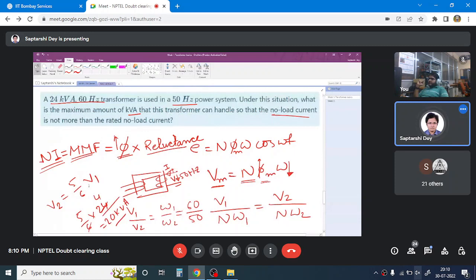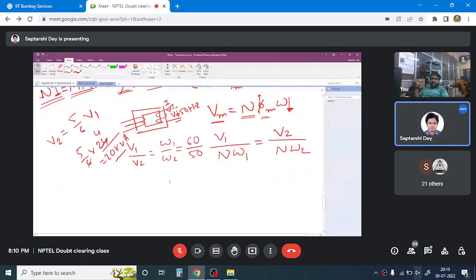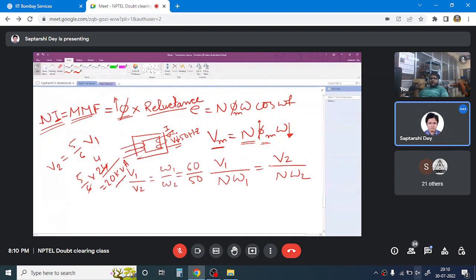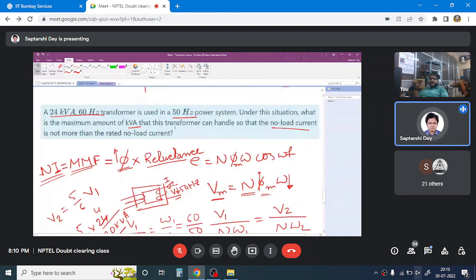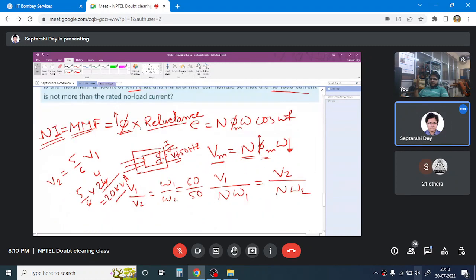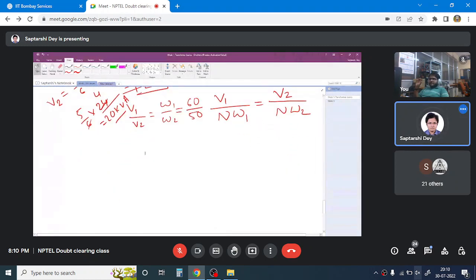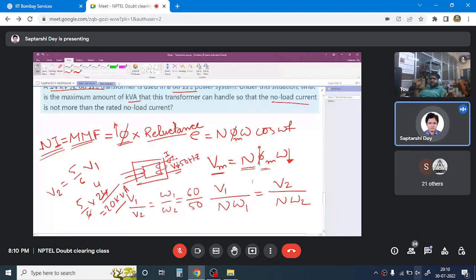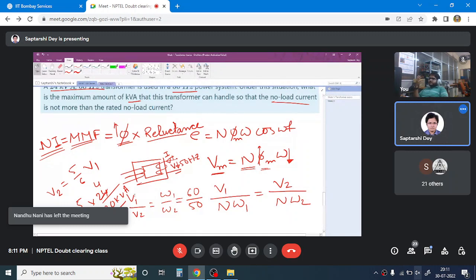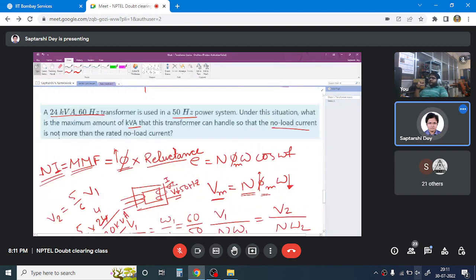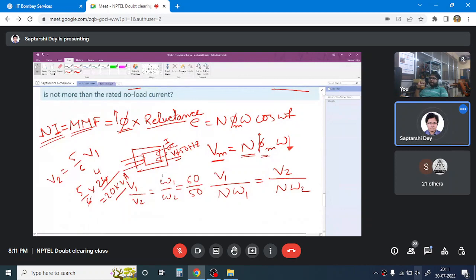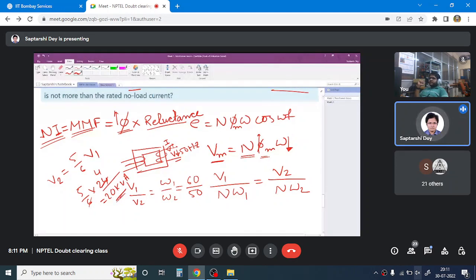See, I had to reduce the voltage. Suppose I had not reduced the voltage, what would happen? My no load current would be more. And there would have been a ceiling, the rated current ceiling, which I would not be able to reach because the flux would be more than the rated. Here I am keeping the flux constant. I told you that we cannot go beyond the rated value of flux, to avoid saturation and other problems. Since I am keeping my flux at its rated value, I have to reduce my voltage so that my no load current reduces and my flux is within the limit. Since my voltage is reducing and my current is not reducing, my kVA rating is simply 5 by 6 times the kVA rating. I will get 20 kVA. This is the maximum I can operate with this transformer.